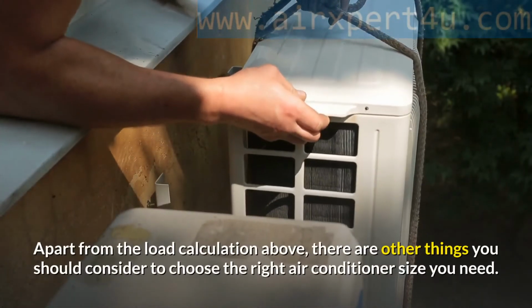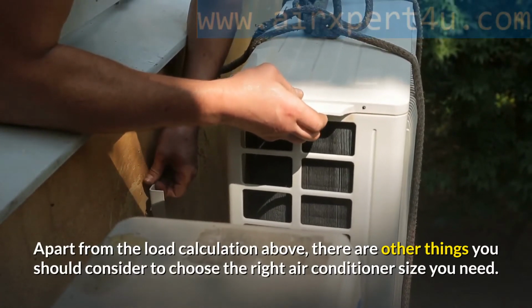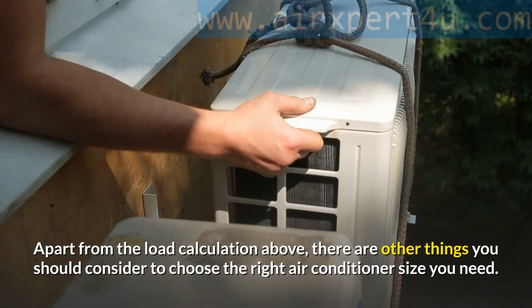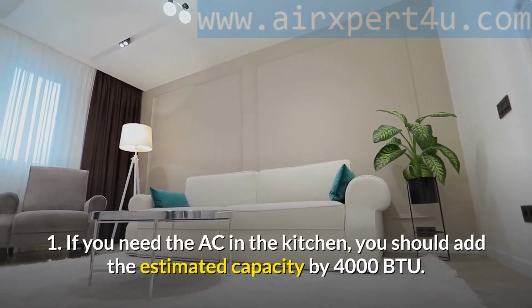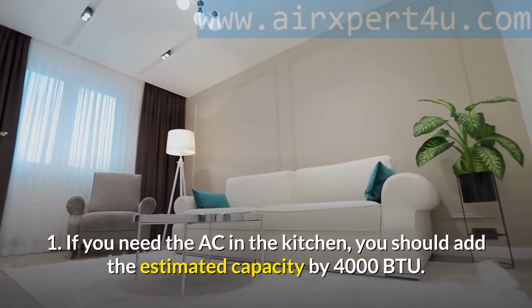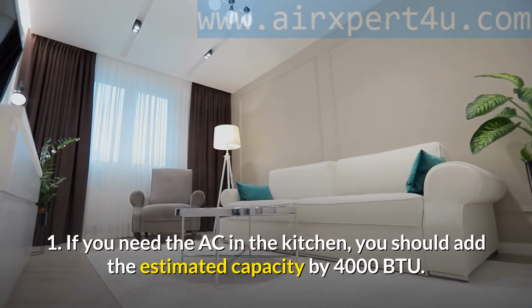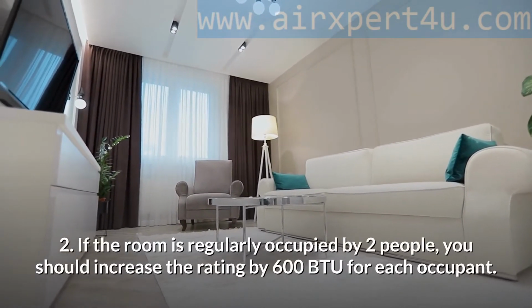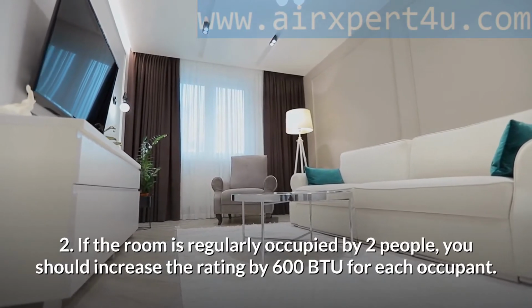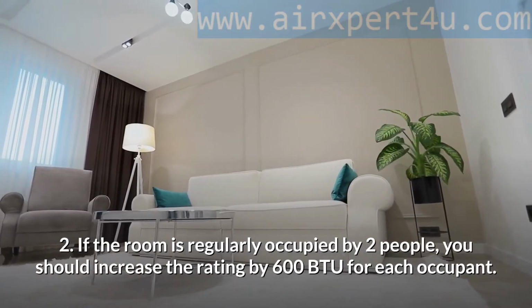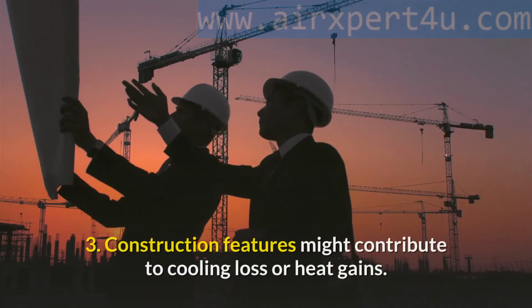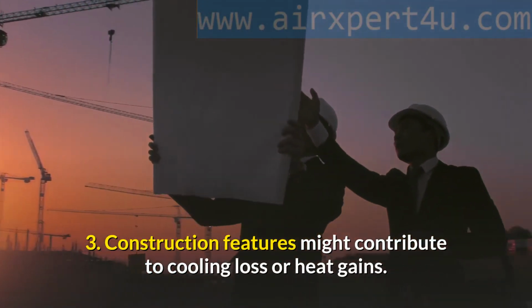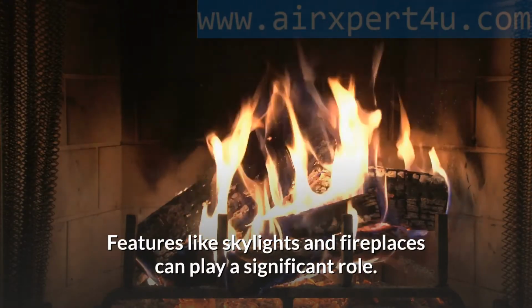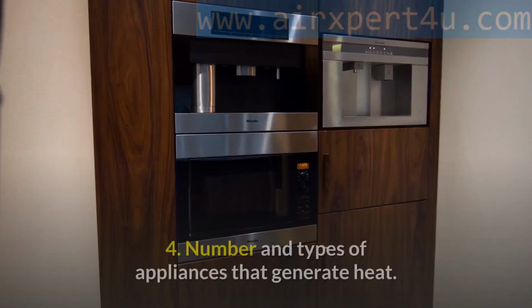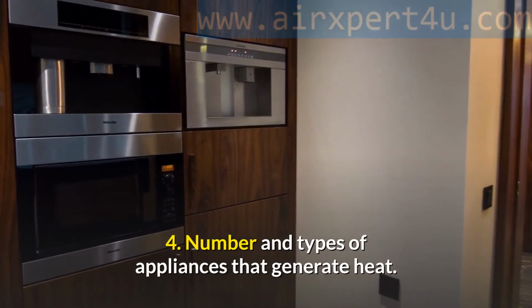Apart from the load calculation above, there are other things you should consider to choose the right air conditioner size you need. 1. If you need the AC in the kitchen, you should add 4,000 BTU to the estimated capacity. 2. If the room is regularly occupied by more than 2 people, you should increase the rating by 600 BTU for each occupant. 3. Construction features might contribute to cooling loss or heat gains. Features like skylights and fireplaces can play a significant role. 4. Number and types of appliances that generate heat.